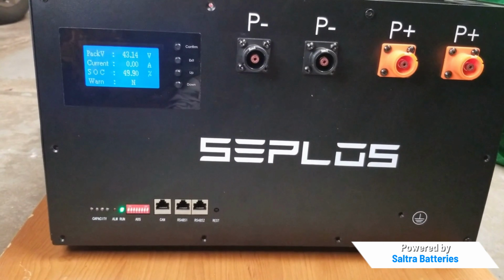State of charge, 49.9%, right in the middle. These cells have been sitting since QA testing. That's normal resting SOC for NaFP cells at storage voltage. Warnings? None. 0 fault codes, 0 alarms. The BMS powered on, recognized all 16 cells, and reported a clean status on first boot.